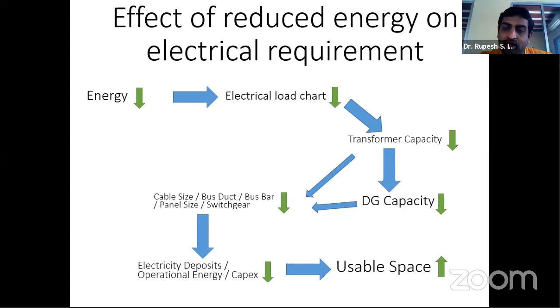How? Because our load charts would come down. A business as usual building may have, just as an example, 4 transformers. We may size it down, and it may require only 2 transformers. So the transformer capacity comes down. The capital that I invest on the transformer would come down, and consequently the DG capacity would come down, because I don't have to invest more on the DG as my load chart itself is lesser. Then the consequent process would bring down my cable size, my bus duct size, my bus bar sizing, and my panel size. The amount of space required for my panel could come down, and my switchgear rating and sizing would come down.